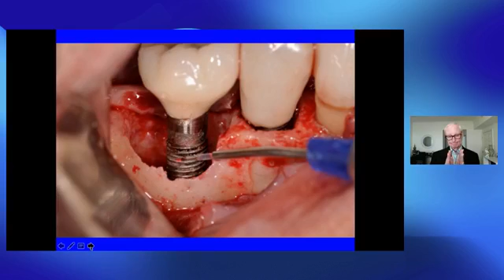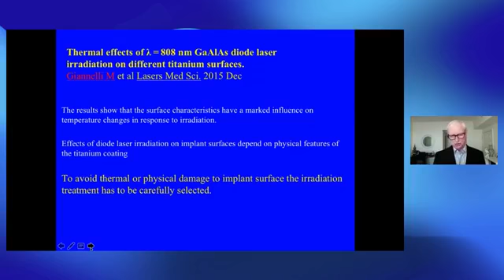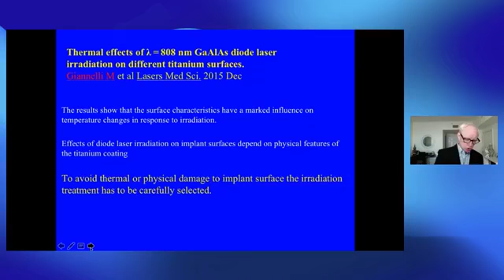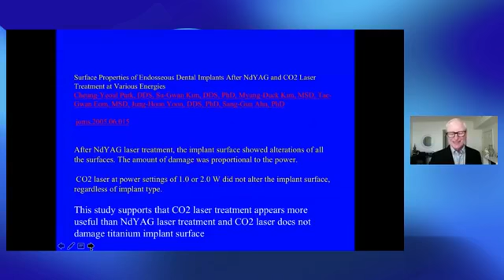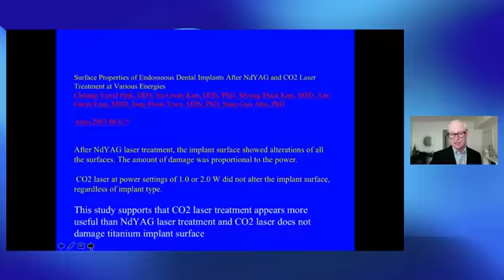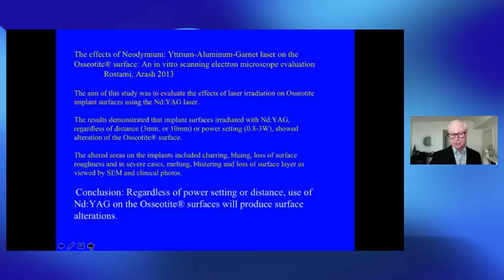To avoid thermal or physical damage to implant surfaces, the radiation treatment has to be carefully selected. In other words, what is the wavelength you're using? What's your wattage? Is it going to be initiated or uninitiated? How long are you going to spend in it? Are you just going to touch the soft tissue inside the sulcus, or are you going to touch the implant itself? What are you really trying to do with the laser if it's a diode? This study supports that CO2 laser treatment appears more useful than the Nd:YAG laser, and that the CO2 laser does not damage titanium surfaces. Conclusion: regardless of power setting or distance, use of Nd:YAG on the Osseotite surface will produce surface alterations.